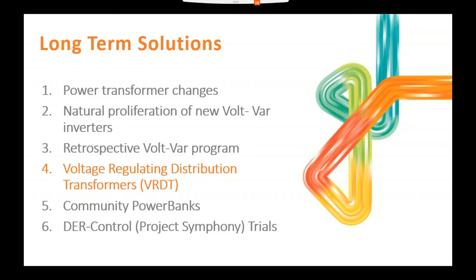In terms of this, we've been trialing 11 distributed voltage controlling transformers. Thomas talked about the method: you typically have a medium voltage run which might already be at the high or low end by the time it gets to your fixed tap transformer, and if that problem continues you get outside of your limits. Dragging those voltages back within prescribed limits with a voltage regulating distribution transformer means your LV customers can be kept within those tighter bandwidths as required.